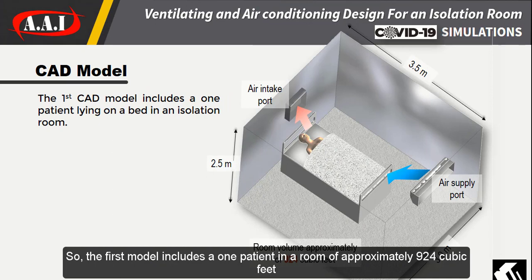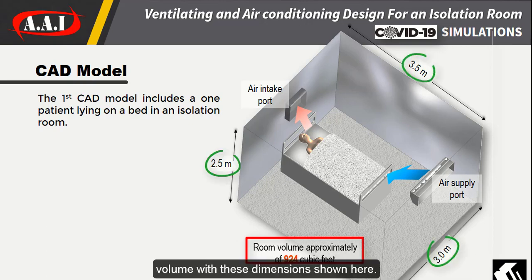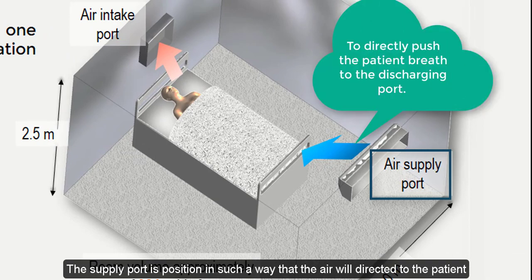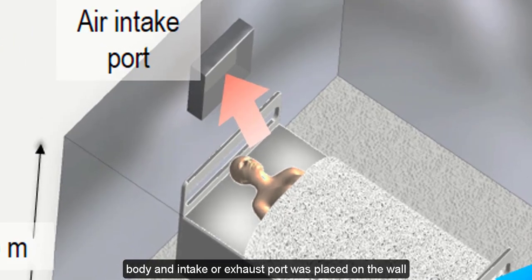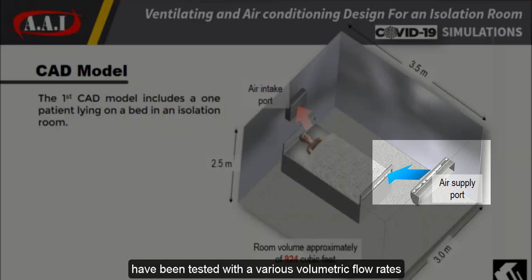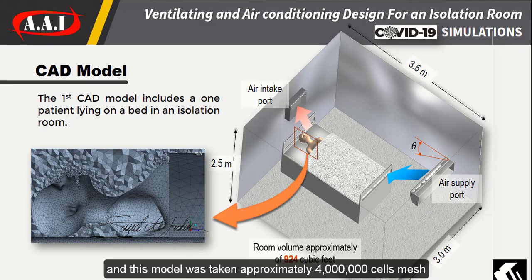The first model includes one patient in a room of approximately 924 cubic feet volume with the dimensions shown here. The supply port is positioned so that the air will be directed to the patient's body, and the intake or exhaust port was placed on the wall right above the patient's head. Different angles of air supply have been tested with various volumetric flow rates, and this model was taking approximately 4 million cells in the mesh.